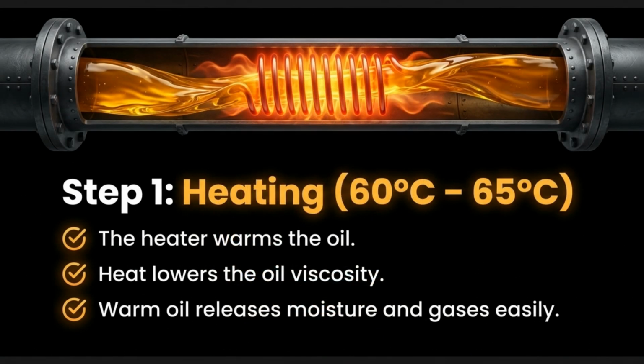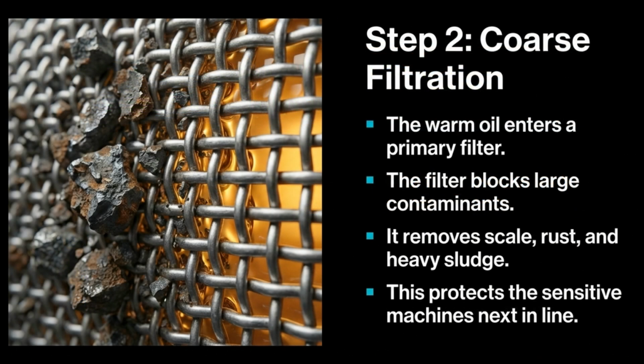Step 1 is heating the oil to between 60 and 65 degrees Celsius. This lowers the oil's viscosity, which allows moisture and gases to be released more easily. Step 2, coarse filtration, involves passing the warm oil through a primary filter. This filter blocks large contaminants like scale, rust, and heavy sludge, protecting the more sensitive machines later in the process.